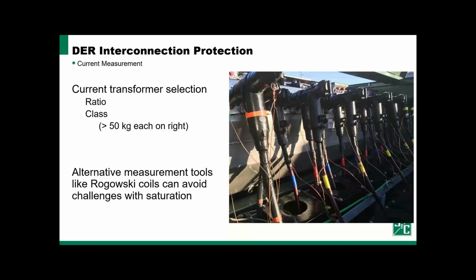Now, there are other tools that can also be used to measure current. One of those is Rogowski coils. Rogowski coils can be linear across a wide range of current and can enable accurate current measurements from single-digit amps up to tens of thousands of amps. This is very effective for microgrid applications. And fortunately, some commercial products enable the use of Rogowski coils with protective devices. One of those is a product that my employer makes, the S&C Interrupter Pulsecloser, a protective device that uses Rogowski coils and can enable detecting both low and high fault current levels accurately.